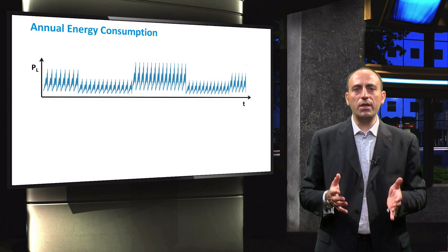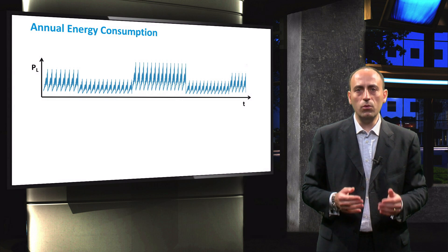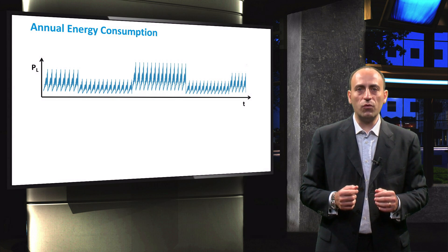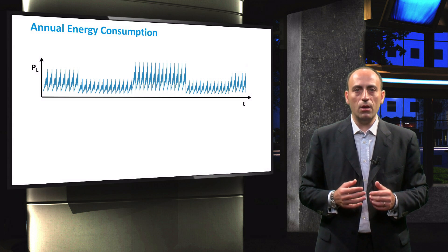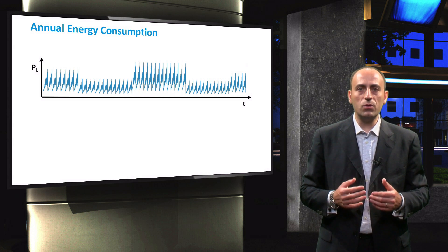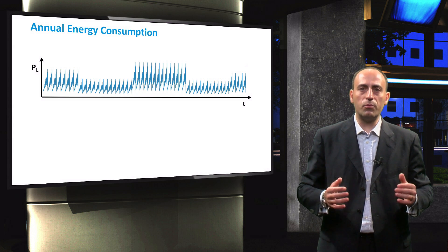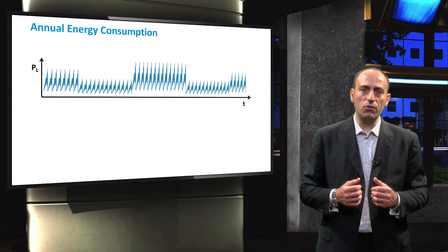The load profile shown here is obtained by analyzing the load consumption in one week. The analysis is performed four times per year — once in winter, spring, summer, and autumn. The one-week load analysis is then used for all the weeks of that respective season. In this way, a full year load profile is obtained. In this load profile, the seasonal variation during the year is clearly visible.